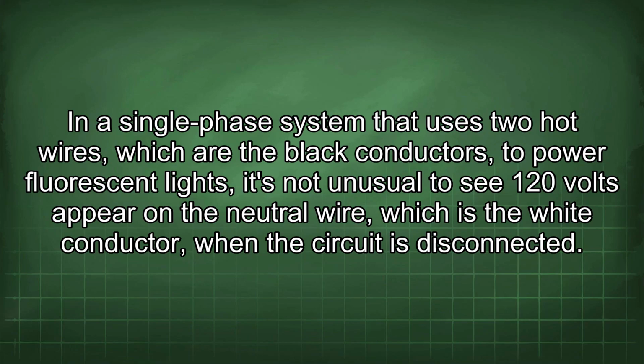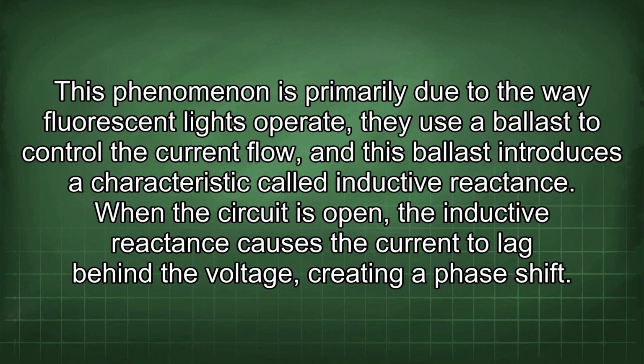In a single-phase system that uses two hot wires, which are the black conductors, to power fluorescent lights, it's not unusual to see 120 volts appear on the neutral wire, which is the white conductor, when the circuit is disconnected. This phenomenon is primarily due to the way fluorescent lights operate.